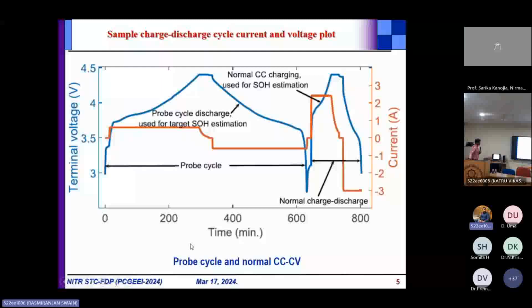The first part shown here is called a probe cycle. A probe cycle is defined such that you apply a very small amount of current. If a battery has a rated capacity of x ampere-hours, the rated current at which it can be charged, the 1C rate, is x amperes. The probe cycle current can be chosen as maybe 1/5 or 1/6 of the rated current, so it's a lower magnitude current.